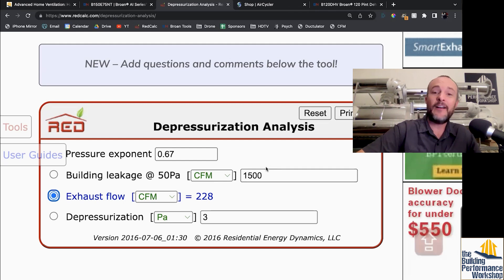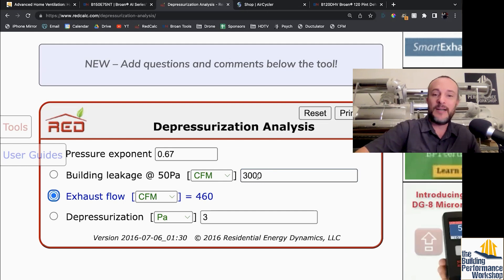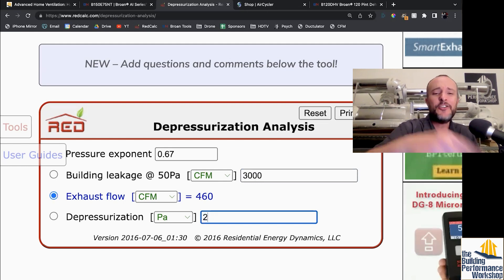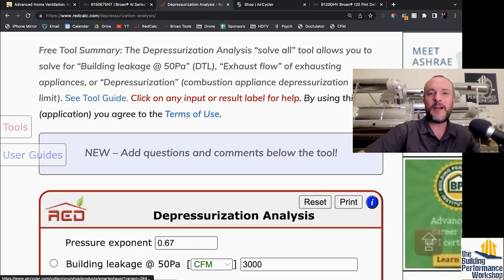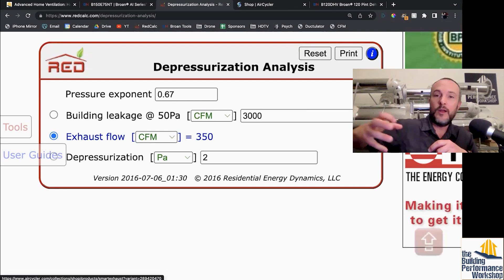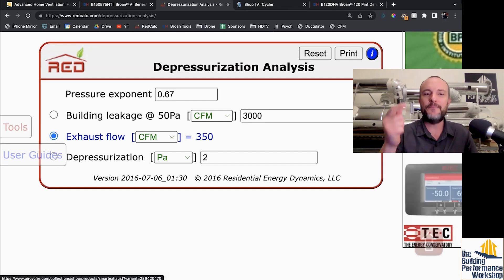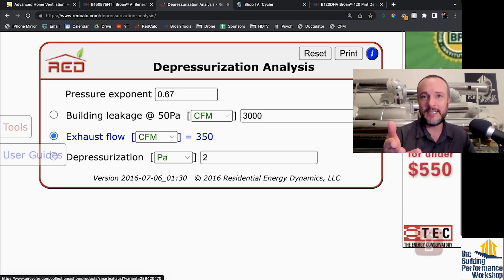So in a very leaky home — like maybe a 3,000 on the blower door — if we wanted to induce even just a two pascal depressurization, remember that when the wind blows it's going to change the pressurizations on the windward side of the house versus the leeward side when the doors are closed. But even just with a two pascal pressurization, we're looking at 350 CFM.